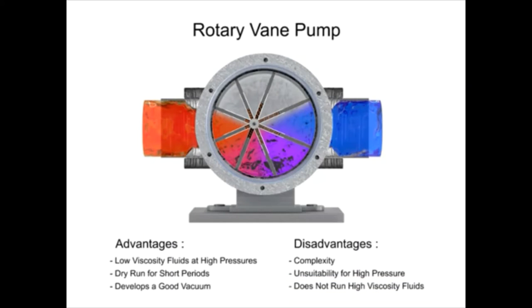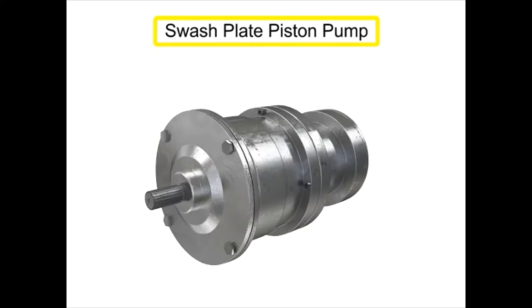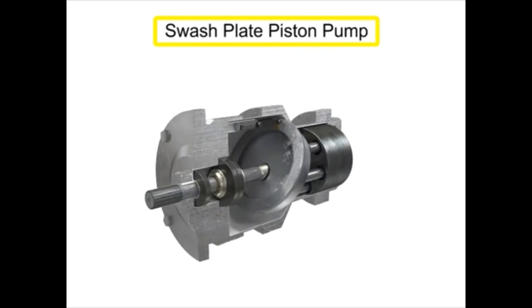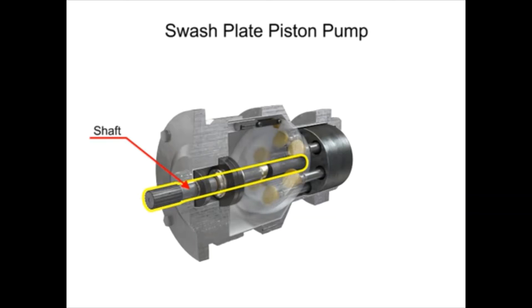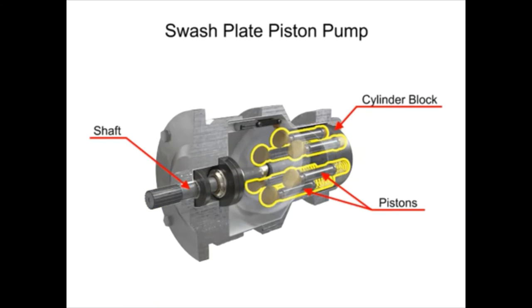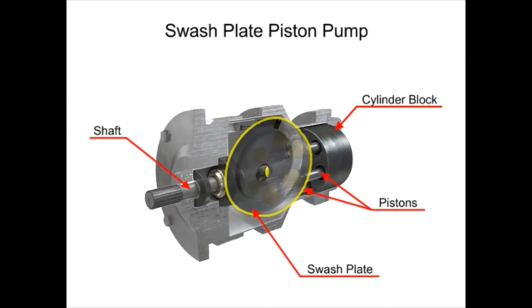Piston pumps come in many different forms. A swashplate is a device used to translate the motion of a rotating shaft into the reciprocating motion of a piston. Swashplate piston pumps have a rotating shaft connected to a cylinder block containing pistons, which are pressed against a stationary swashplate that sits at an angle to the cylinder.